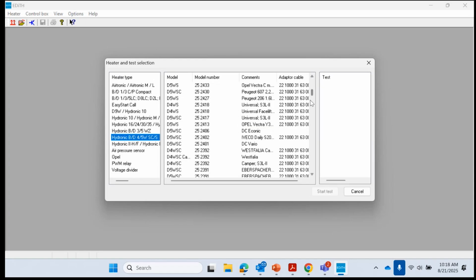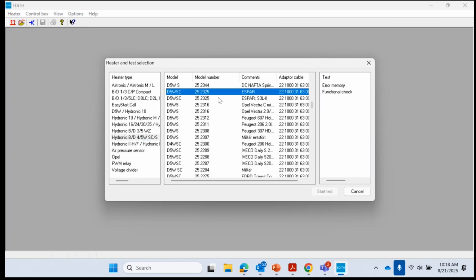The model number typically for the first generation will be a 25 23 25. So let's locate that in this list over here: 252325. There we go. We can see that's the one right there, but you'll see there are two of them. When I click on the one above, it only gives me two tests, a memory and a functional check. So that's an older version, whereas the newest version with the same model number has three different tests.